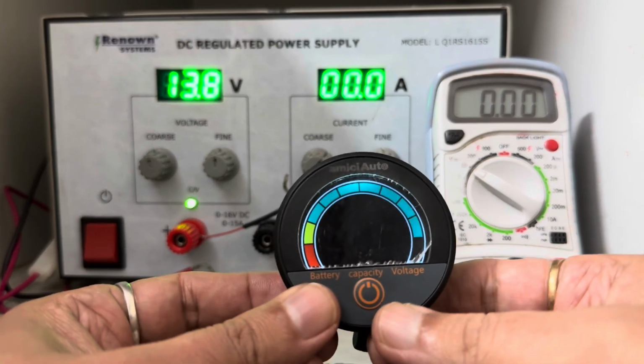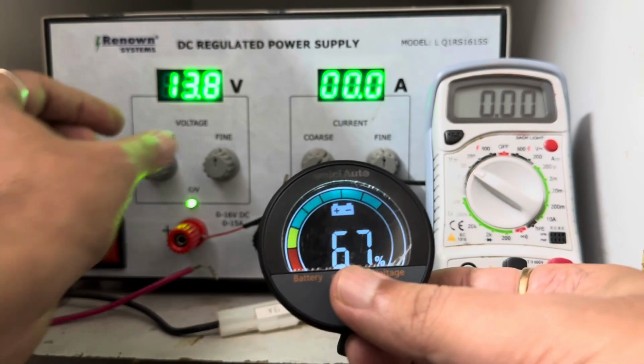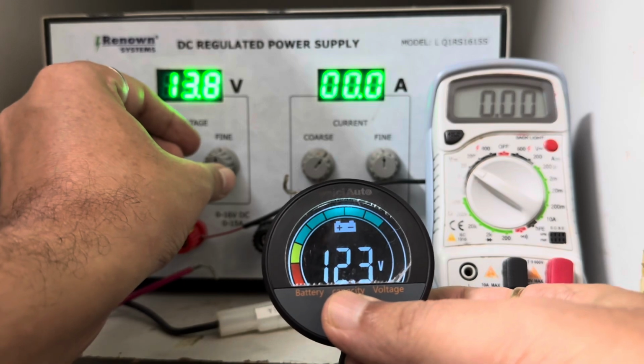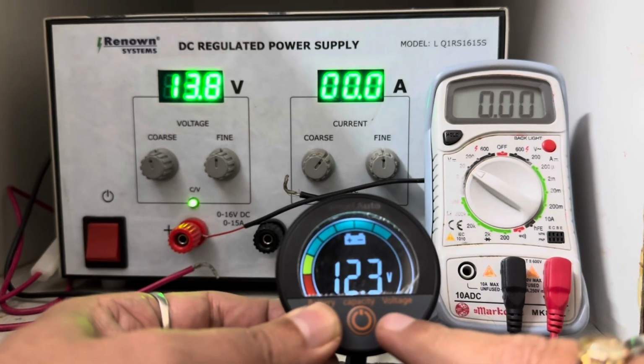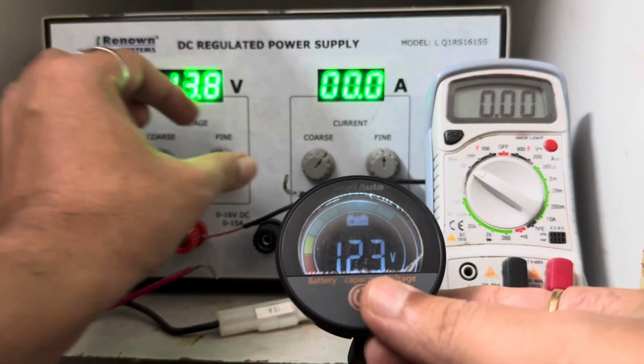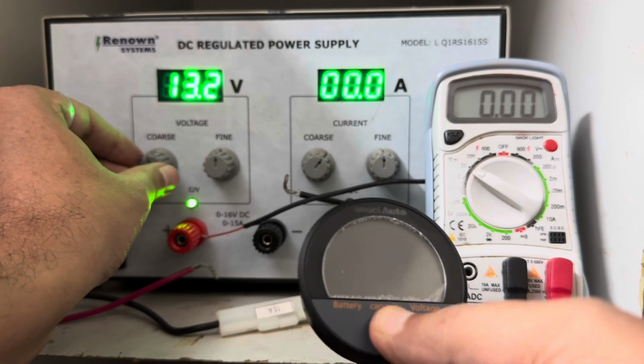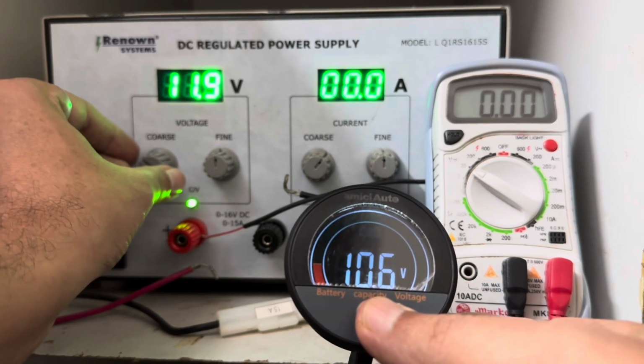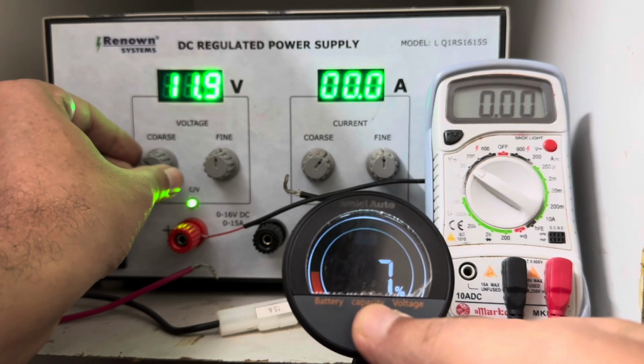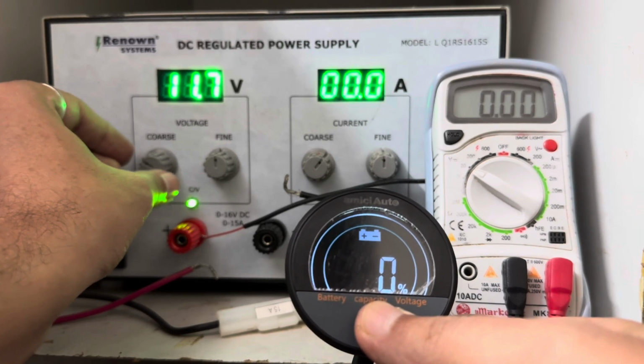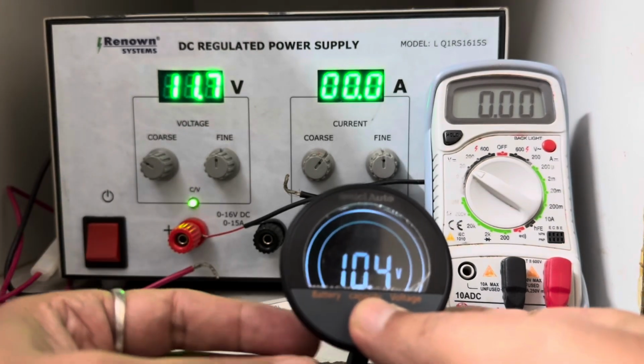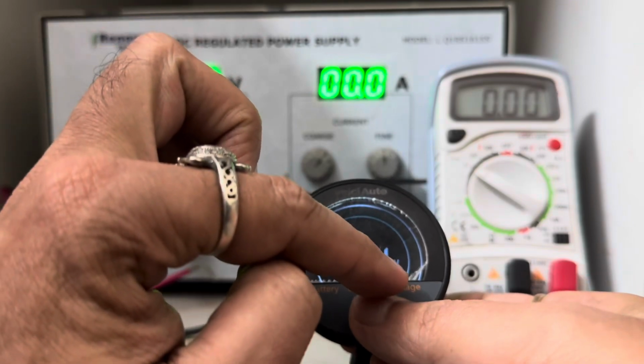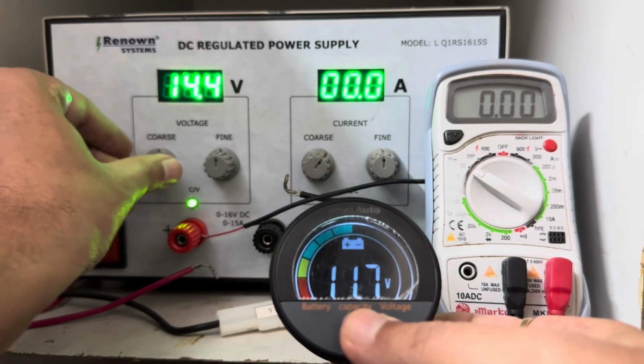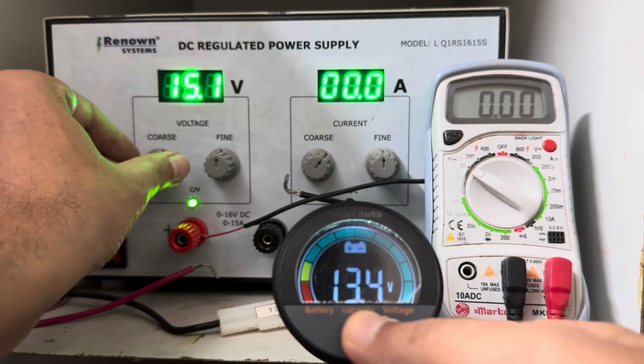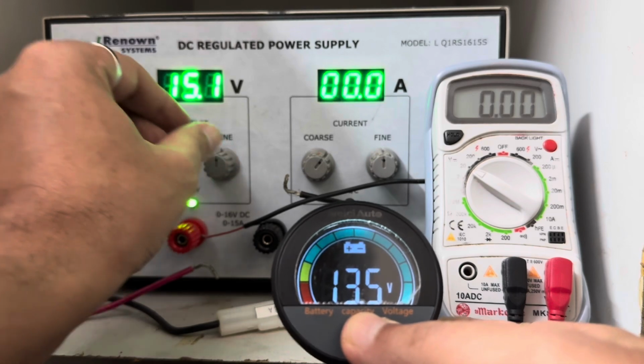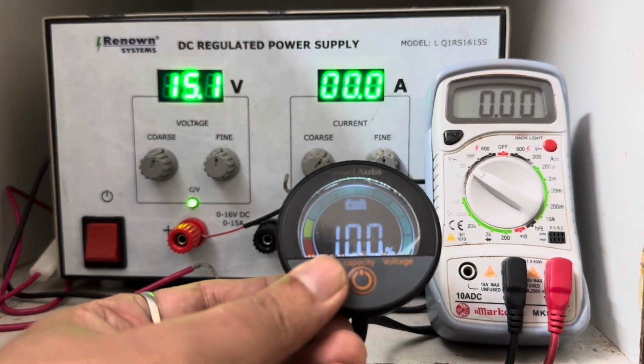Restarting it, so this shows 67%. Let me go to the actual voltage on this voltmeter. At 10.4 volts, it shows 0%, confirming that 0% corresponds to 10.4 volts. Now going to 13.5 on the voltmeter, that shows 100%. So that's the calibration done internally in the settings.